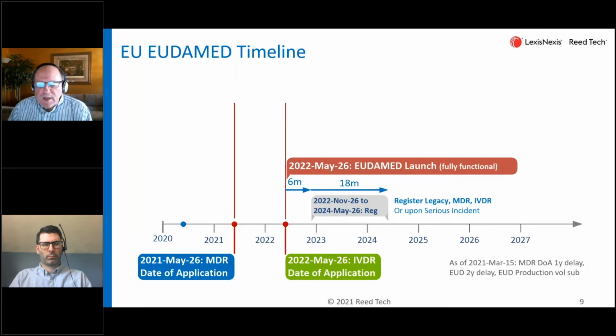The EUDAMED database, used to store a lot of this information, is now scheduled to be fully functional as of May 2022. There's a 6-month period following that announcement, which is the beginning of an 18-month required registration period for legacy devices, MDR devices, and in vitro diagnostics. You do need to register immediately upon a serious event, as that's a precondition to reporting a serious incident to the EUDAMED vigilance module.